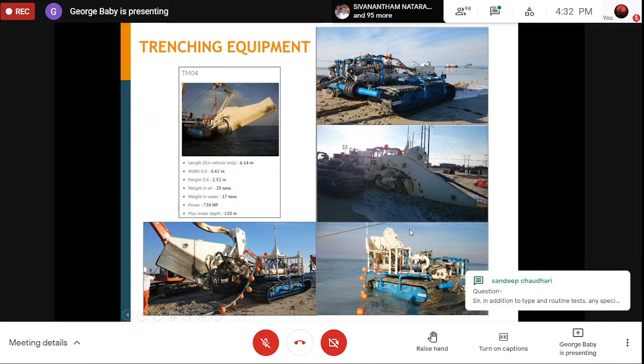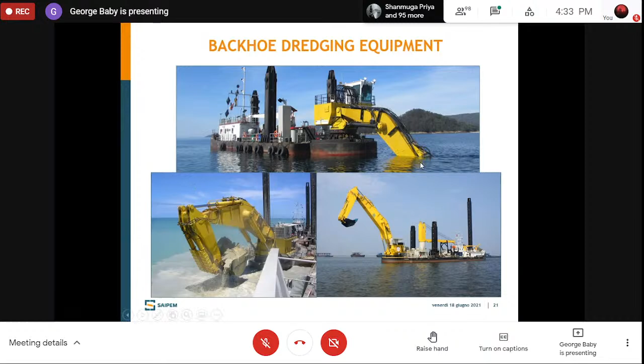In some cases, so many cables are laid in parallel that we don't use the previous method, which is the cutting or burial method. So we use these trenching equipments. Trenching equipment is like what we have in India, the JCB kind of equipment. This will be attached to the ship, and it will remove the sand and soil and make a trench. The cable will be laid on top of this trench, and after laying the cable, either it will be naturally covered, or we bring some equipment on top of it and cover it again with soil.